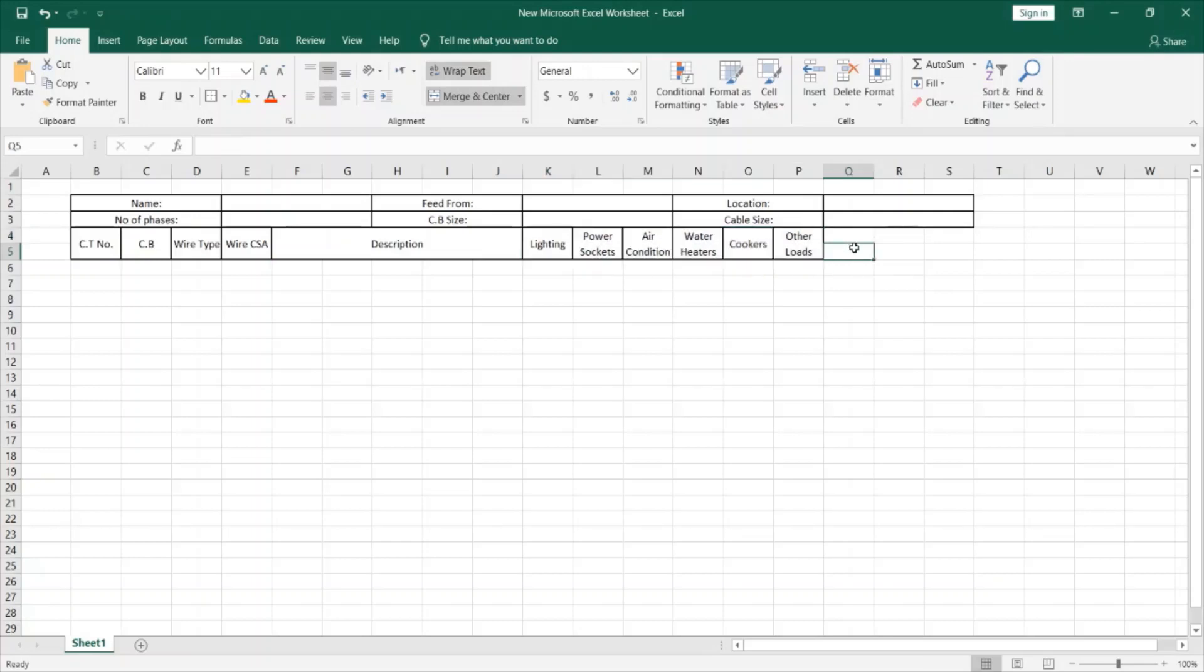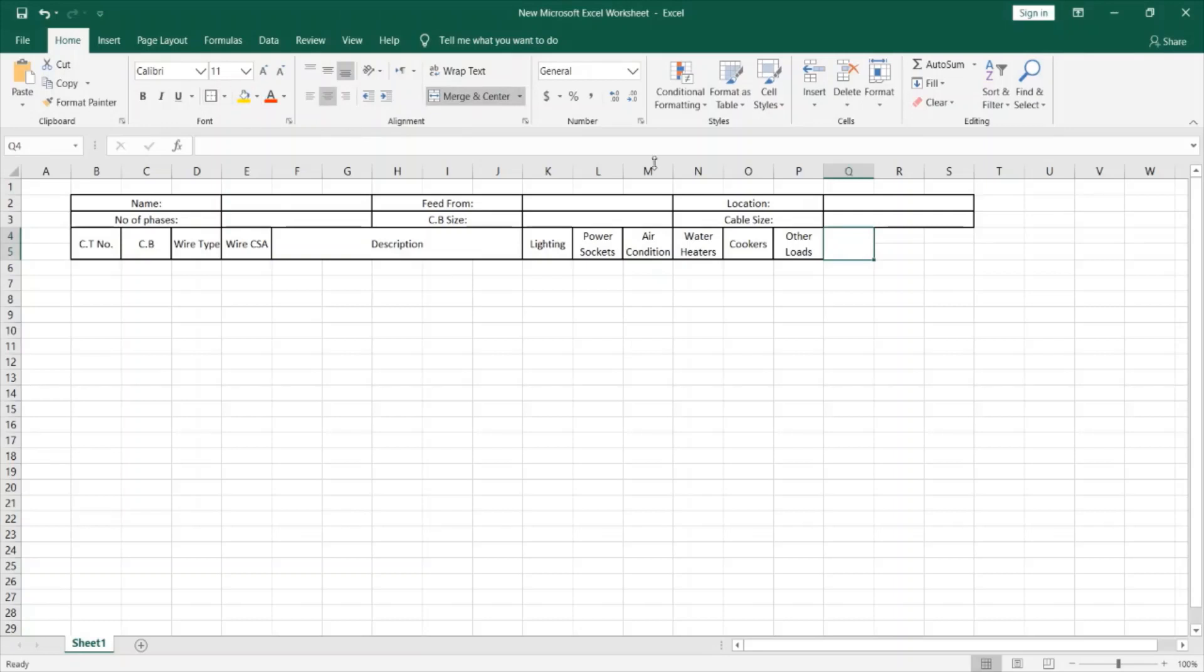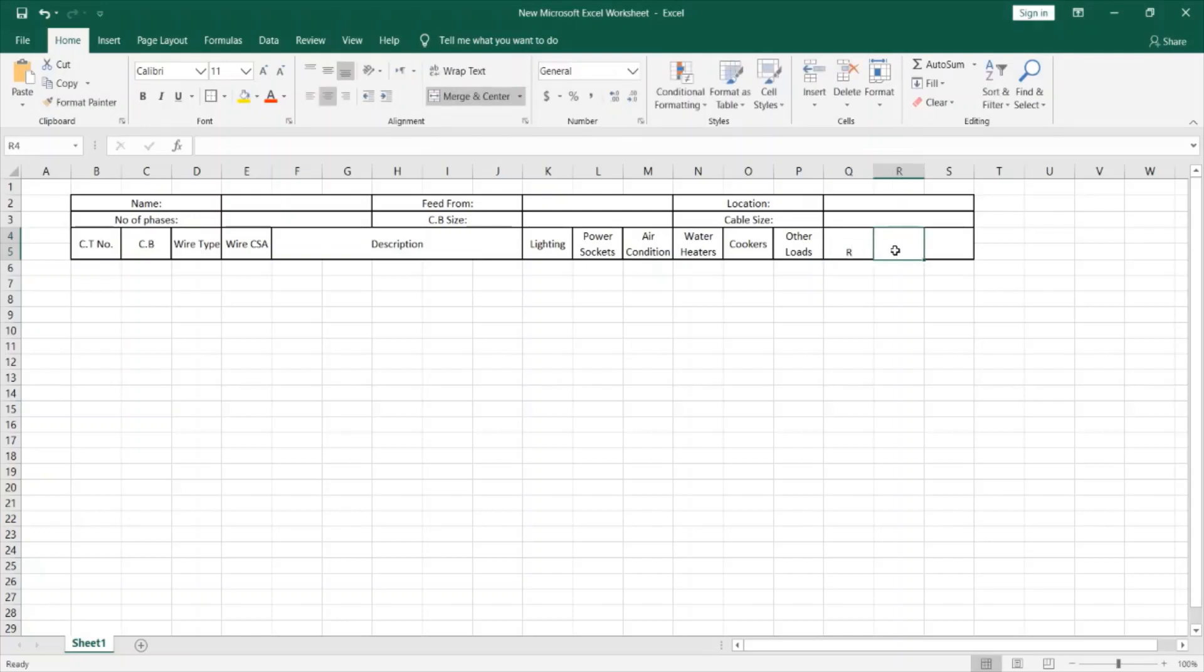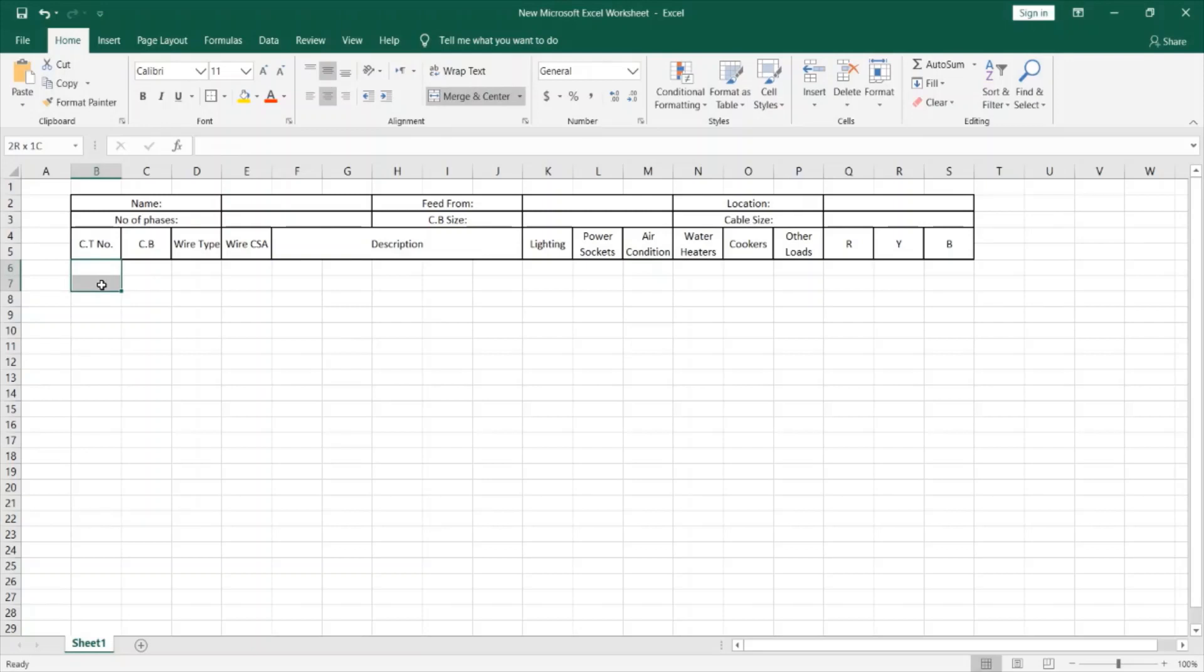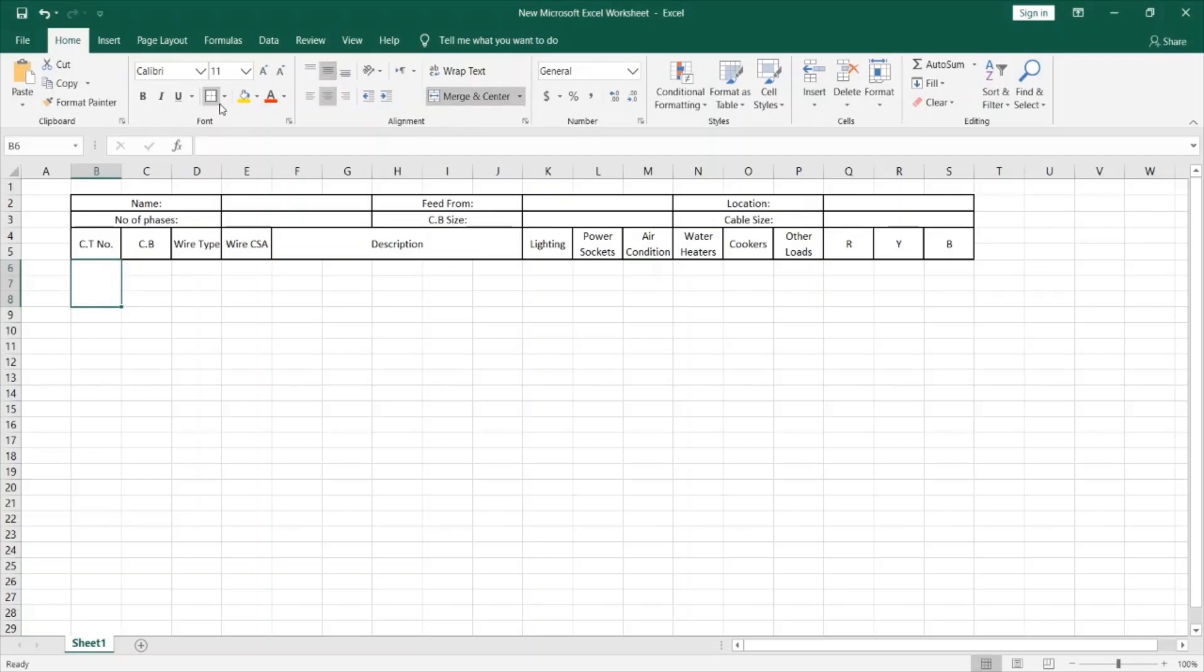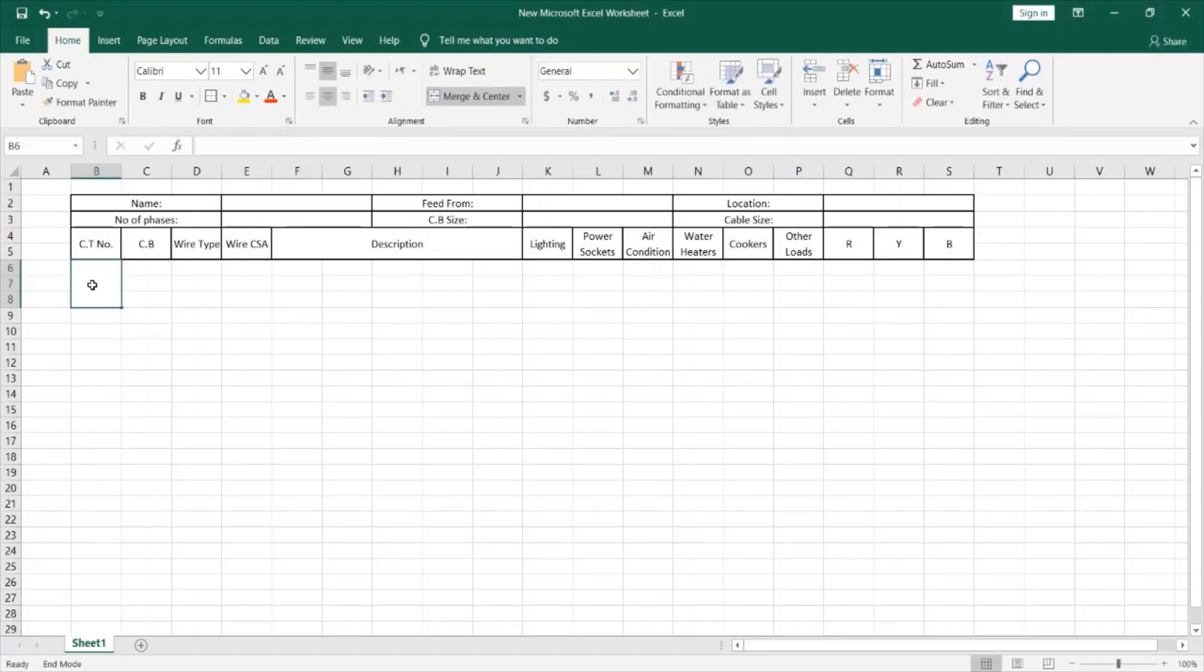Now I will add three more cells over here to indicate the R, Y, B phases. I will call this R, this one Y, this one B. Since the DB is three phase type, we can merge three phases or three cells just in one cell for the circuit number. What I mean is, I will select three circuits because each of these cells are going to indicate one circuit. And I'll click on merge and center and give it a boundary as well. And call this one.